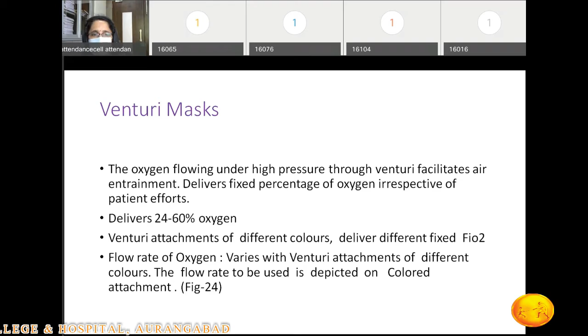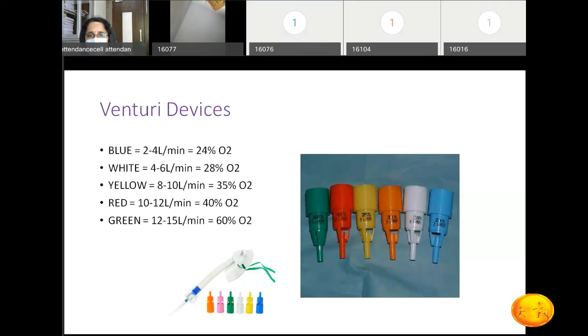There are various colors of this Venturi mask. You see blue, white, orange, yellow, all these colors are there, and the oxygen concentration to be delivered by each attachment, this Venturi valve, is given over here, and how much flow rate is to be kept is also given. This is written on these valves. If you want to give a lower concentration, that is 24%, then a flow of 2 liters per minute is to be kept. For the highest, 60%, a flow of 15 liters per minute is maintained. So patients who require a fixed concentration of oxygen, Venturi devices are useful. It is particularly used in asthmatic patients, where not too much oxygen should be delivered.